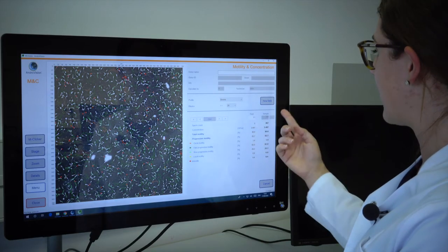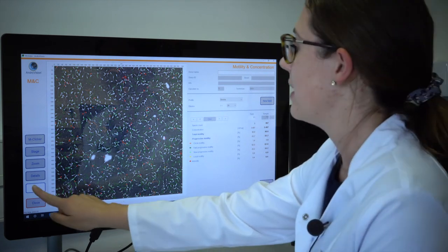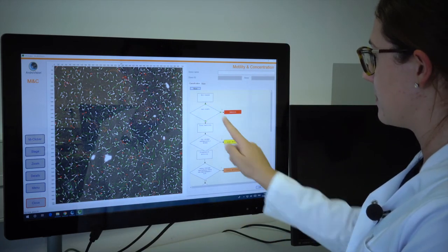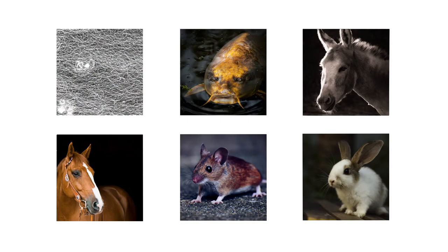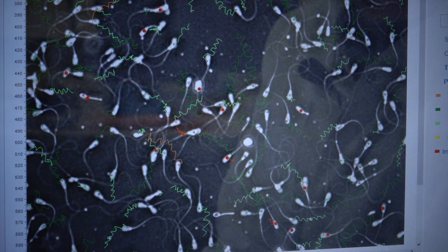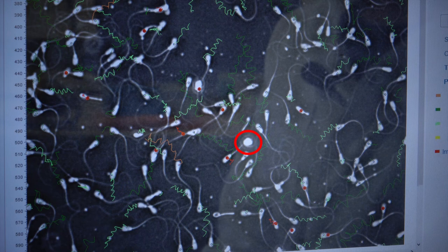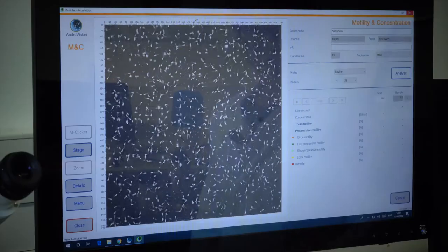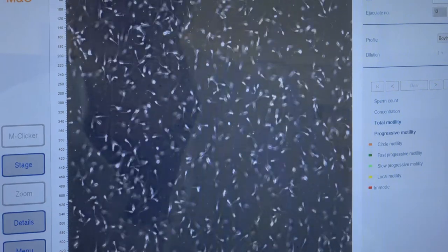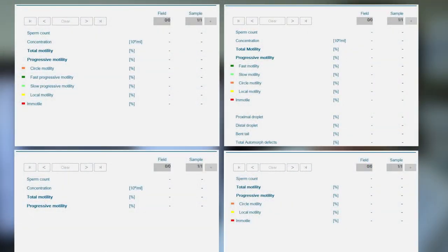During the analysis, sperm cells are counted and their motility is tracked and classified. AndroVision comes with standard parameters which can be adjusted to specific needs and species. AndroVision works very accurately and is able to distinguish between semen cells and debris or egg yolk particles by using a specific particle filter. Additionally, it clearly identifies immotile cells even if the semen sample is drifting through the picture. The user interface showing the results is flexible and can be set individually by each operator.